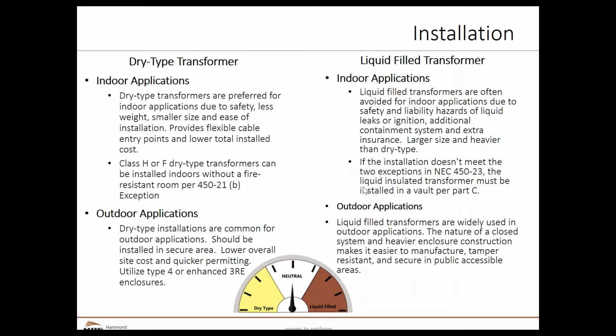With a liquid filled transformer, if I install it indoors, I do have to take certain precautions. Even if I'm using an ester oil, let's say, that has a high flash point, and may not need a fire resistant room depending upon the local codes, I still have to be able to contain all that liquid, either with a separate box that surrounds the transformer, or I would have to dike the whole room. This would also apply if I install a transformer on a roof or something like that, where we have to be concerned if that oil is leaking. Again, not all of the modern stuff like ester oils requires a full vault, but for the most part, there is definitely some additional installation cost and lack of flexibility if I'm using a liquid filled transformer.